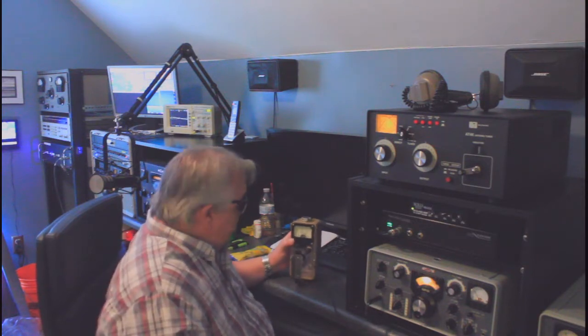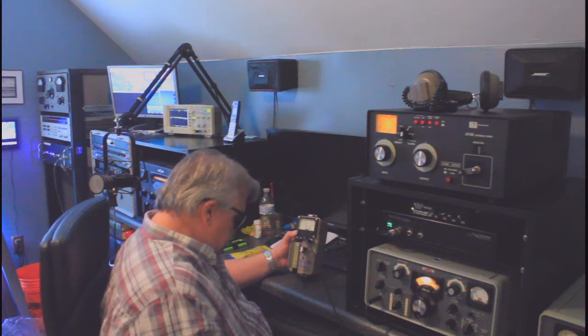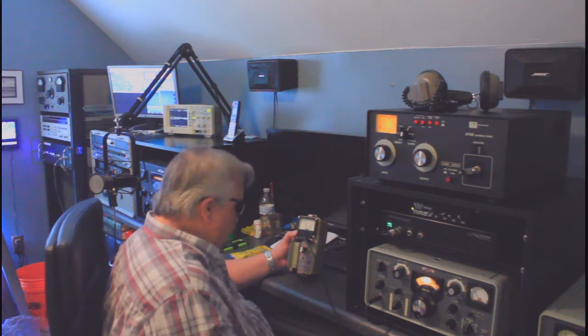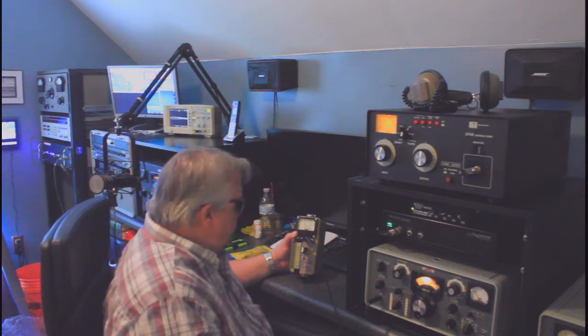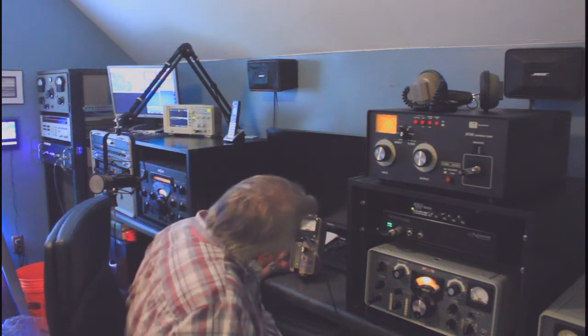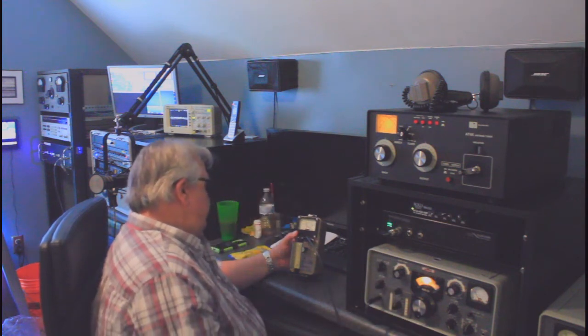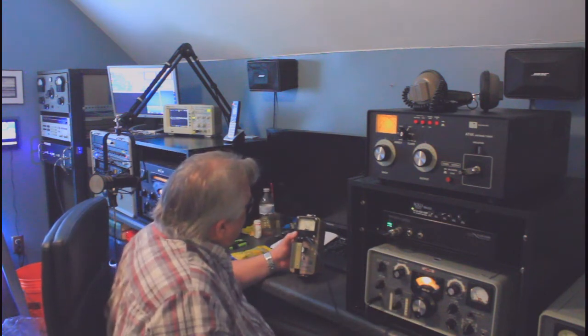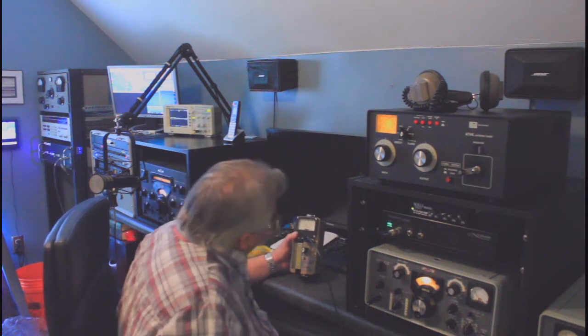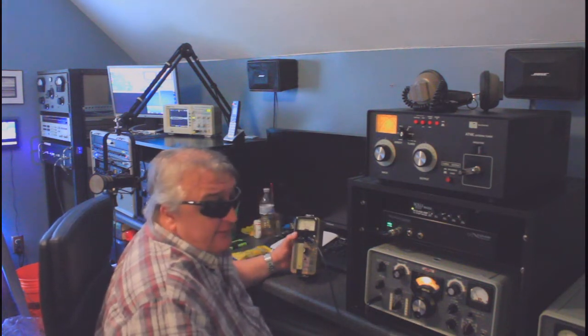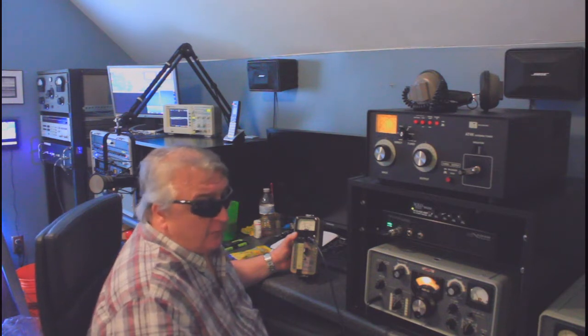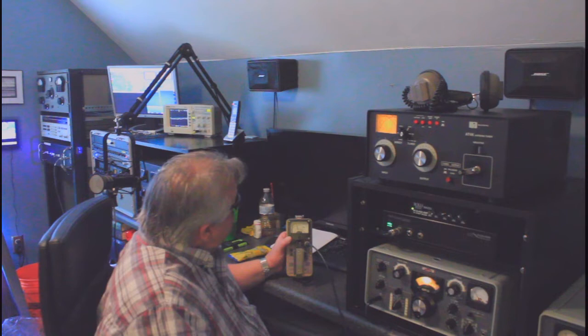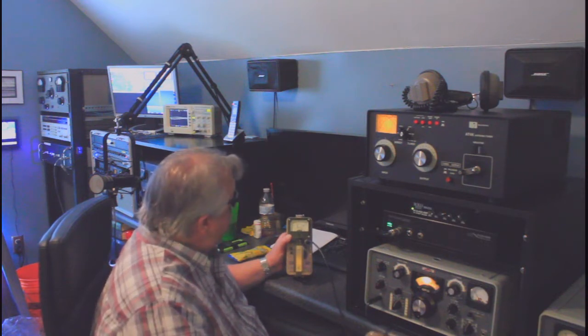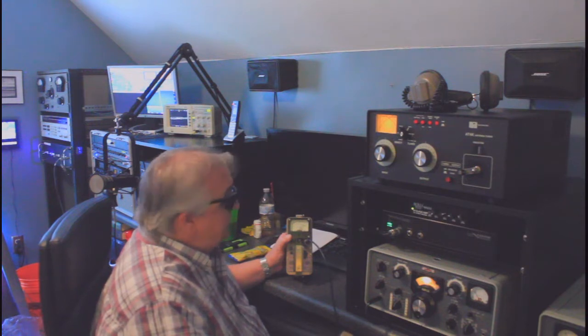Now the head is turned away from me, and we're receiving right now about 200,000 counts per minute. Let me see, is that correct? No, that's 20,000 counts because that's on the 100 scale. Aimed away from me, the back of the pancake probe is basically a sheet of metal. So let's have you watch the needle as I rotate the probe in my direction. Climbing.